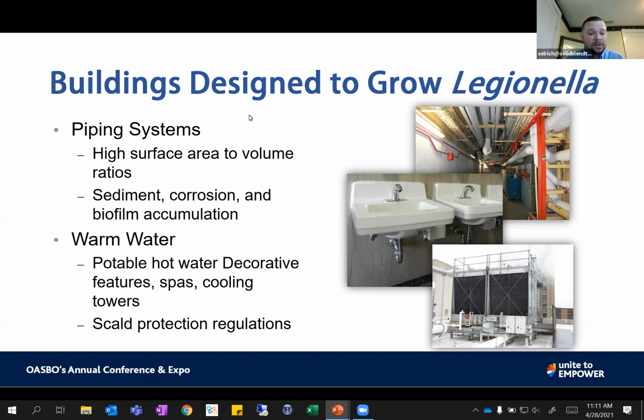But the reason buildings are designed to grow Legionella is that you've got high surface area to volume—think of a domestic plumbing system with miles of pipe in these buildings. A lot of times you've got low water flow or low water usage, and you can have sediment, corrosion, and biofilm accumulation in the piping system, which is all normal for commercial buildings and schools to have.